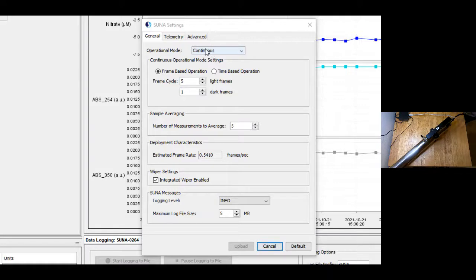You have a couple different things here. You have a frame-based operation. I did 5 light frames to 1 dark frame. So a light frame is what you take when you actually take a measurement when the lamp is on, and a dark frame is you take it when the light is off. The reason why you do that is because that's how you characterize the background electronic noise in the spectrophotometer. And then we can subtract that out and get the correct nitrate concentration.